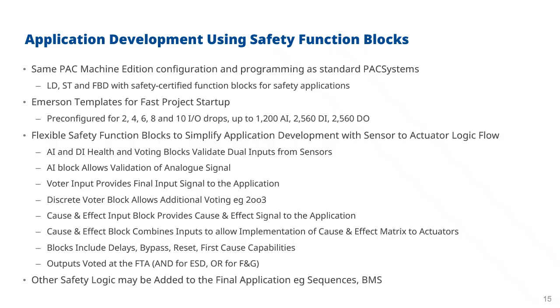Now, outputs don't necessarily need to be voted inside the system. Outputs are actually voted at the field terminal assembly. So typically you'd use an AND arrangement for ESD. So both outputs have to be on. If either output goes off, then the system trips. But for fire and gas, where you want to energize a valve, normally it's the other way around. It's an OR, one out of the two function. So as soon as one output comes on, that's when you trip the deluge of whatever your fire and gas extinguishing is. So they're normally voted at the FTA. So all you need to do in the logic is just turn the two outputs on, and then the hardware will take the rest of it.